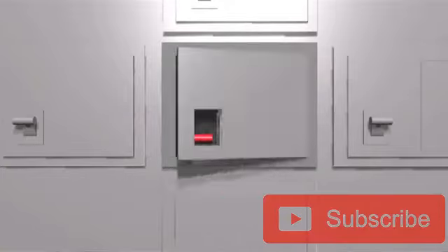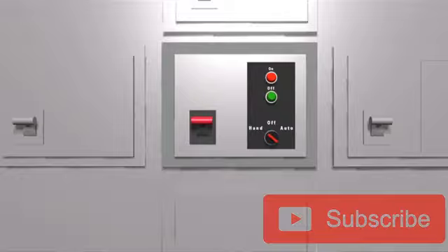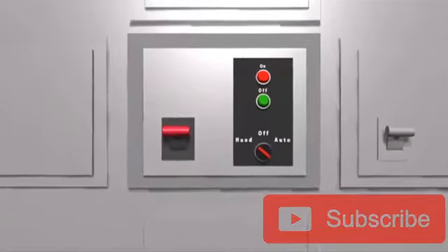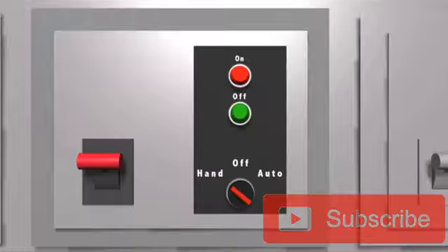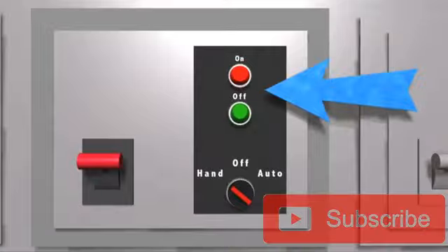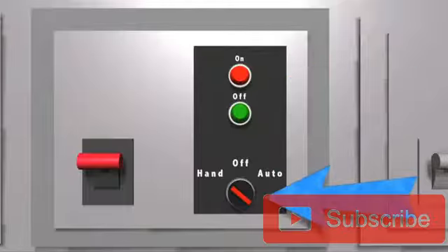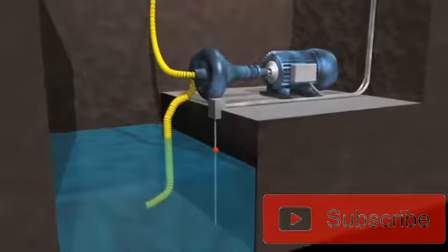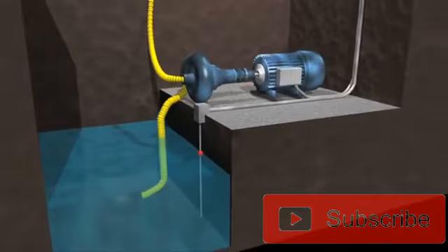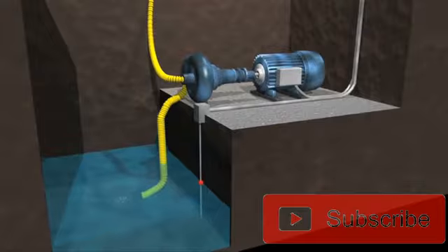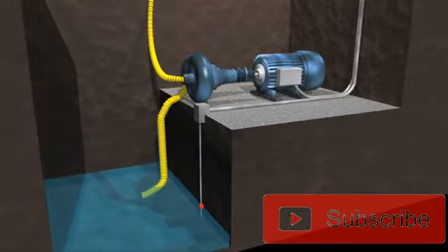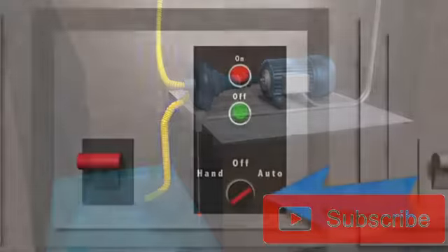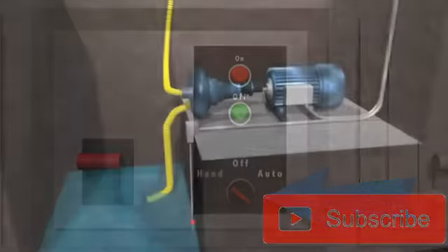There is also a combination motor starter. These consist of the same disconnect switch and breaker, but also have two other features. It has a start-stop switch to manually turn the motor on and off. It also has a hand-off-auto switch. When this switch is in the auto mode, it allows another source to control the motor. A good example of this would be a sump pump. A float switch that is switched on by rising water will control the sump pump. The motor will be turned off when water levels go down and reset the float switch to the off position. When this switch is in the hand position, the motor is always on.